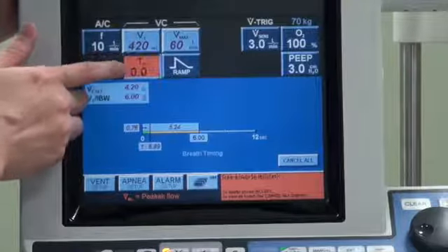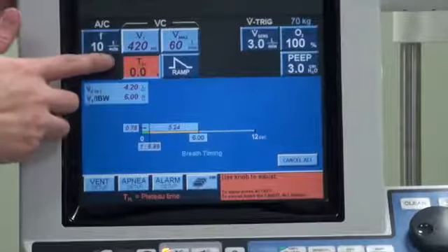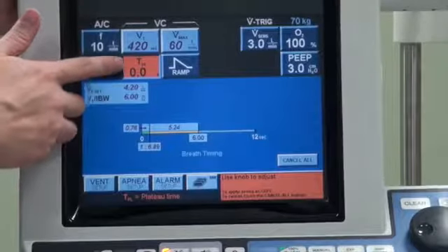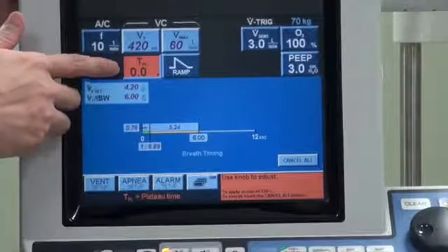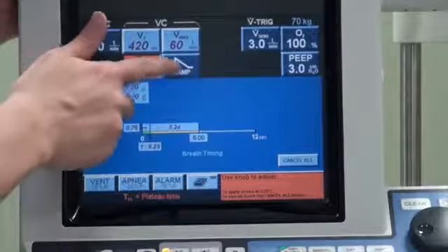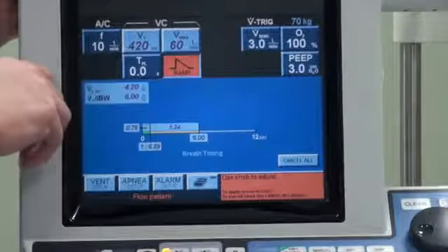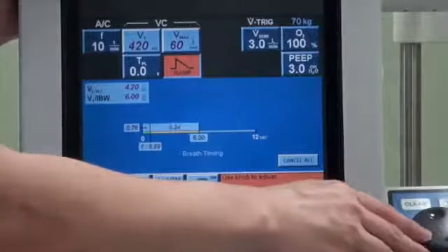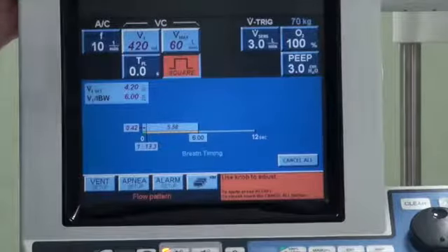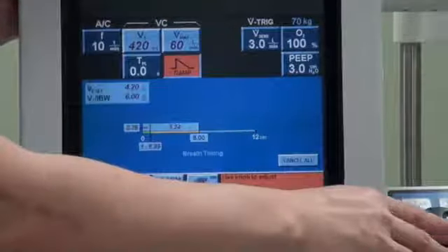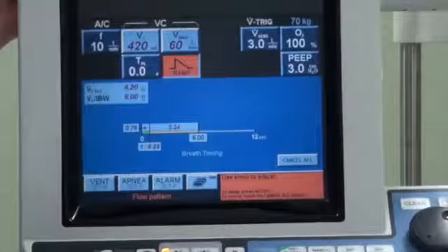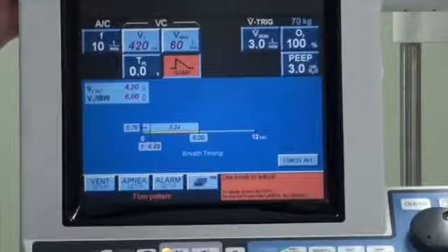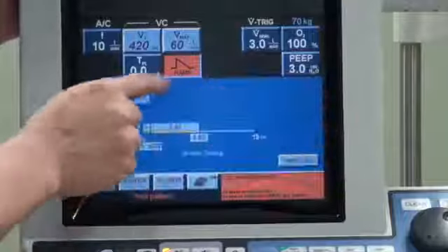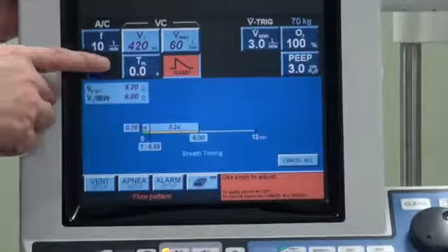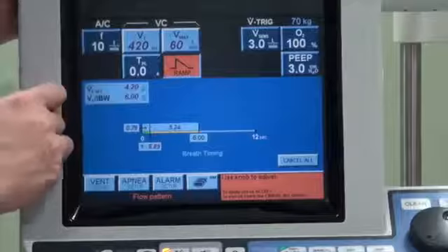T pause time is the time spent in inspiration after the delivery of a breath. For patients on volume control, typically we put that at 0. The waveform will tell you how the flow is being delivered. Is it constant, which means that the ventilator will deliver that flow at a very, very constant rate, or a decelerating mode, which is more physiological for the patient, which means that it's faster at the beginning and then it slows down. So typically we'll put the waveform as a decelerating waveform.